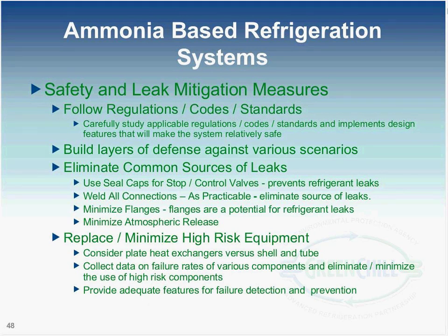The order of descending leak potential goes from flexible hoses to valves to heat exchangers, and very little in piping and pressure vessels. Provide adequate features for leak detection, failure detection, and prevention so that you can shut down some of the systems where you realize a leak.